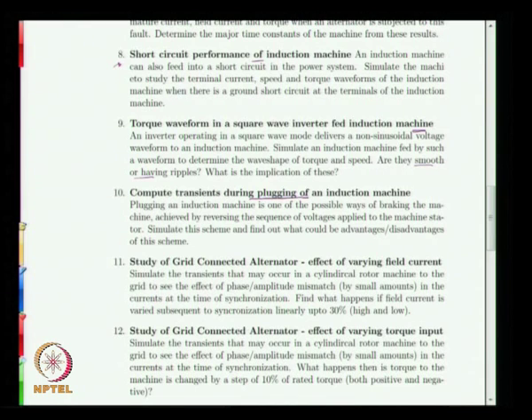The eighth assignment: braking an induction machine by reversing the phase sequence of the stator terminals. Reversing the phase sequence causes the stator field to rotate in the opposite direction to the rotor, producing very severe braking action and stopping the machine very fast. Though not advisable on a physical machine due to severe shaft stress, one can study this in simulation to see what really happens.